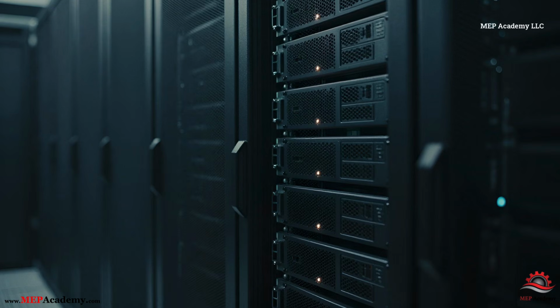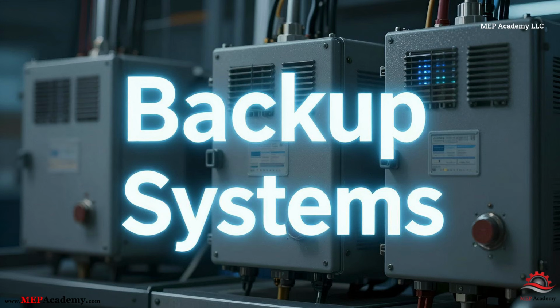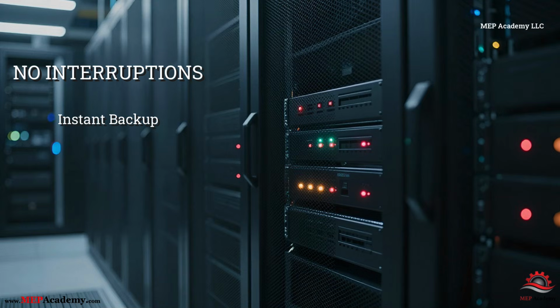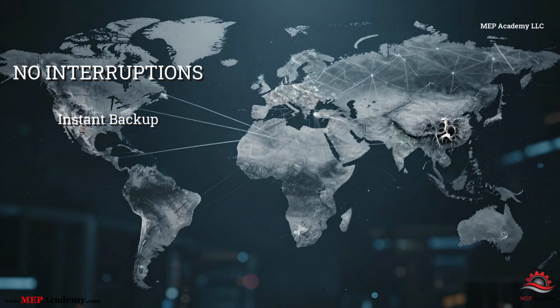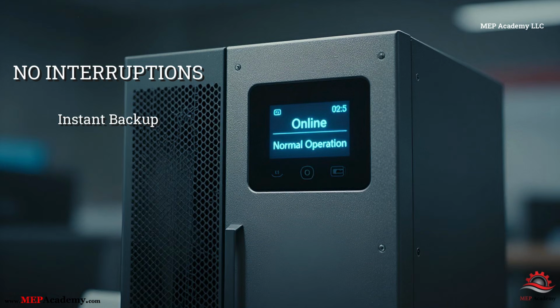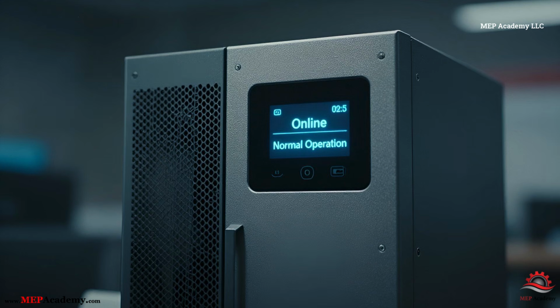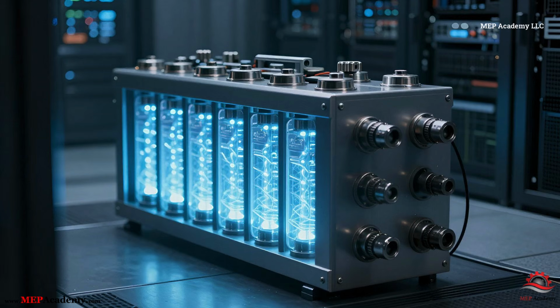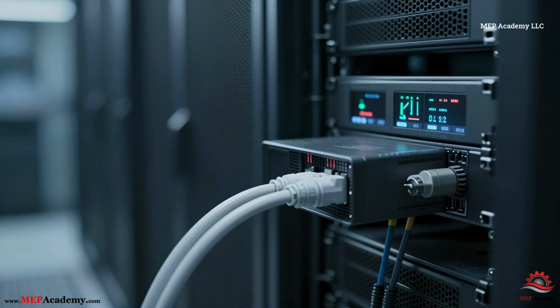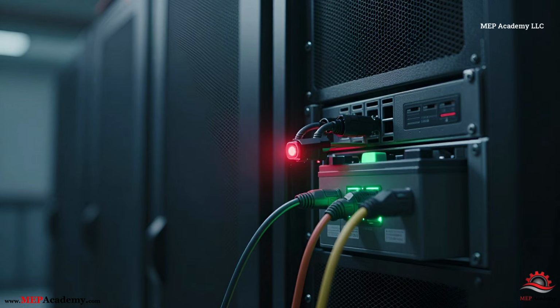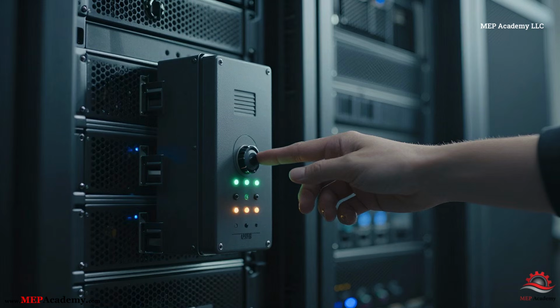But simply distributing power isn't enough. Data centers must also protect against interruptions. This leads to the second critical concept: backup power systems. Unlike most buildings, data centers cannot tolerate even a brief power outage. A momentary interruption might reboot thousands of servers and disrupt services around the world. To prevent that, data centers rely on uninterruptible power supply systems, commonly called UPS systems. UPS systems act like massive electrical batteries. When utility power is flowing normally, the UPS conditions and stabilizes the electricity before it reaches the servers. But if utility power suddenly fails, the UPS instantly switches to battery power. This transition happens so quickly that servers never see an interruption. The UPS system keeps the servers running long enough for the next layer of backup power to start.